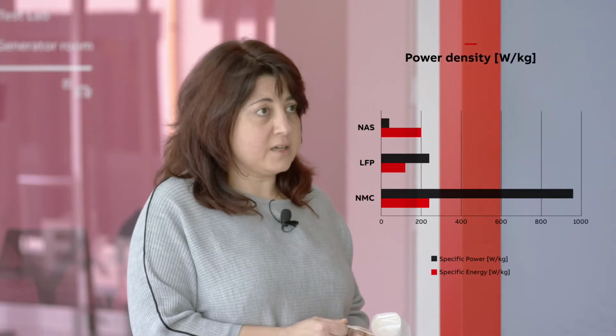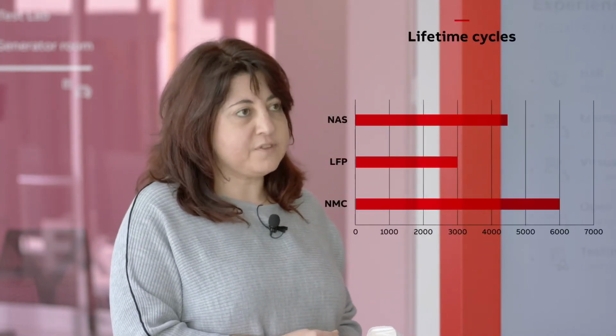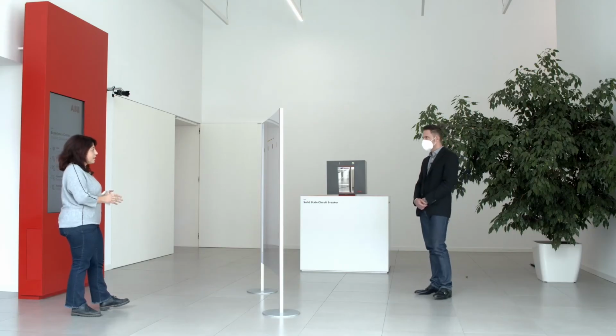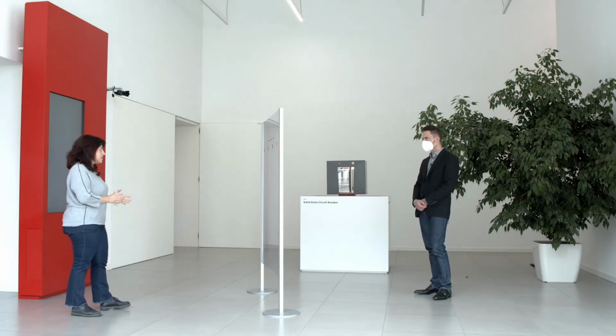The performances of this technology are always very good because the energy density of the cell is around 200 watt-hour per kilogram, and the lifetime is also very good. The same as the lithium-ion battery, the sodium-sulfur battery also has a low intrinsic safety level. This means that for both technologies, it is necessary to integrate in the energy storage systems the proper protections and battery management system in order to reach an adequate level of intrinsic safety, to avoid abuse conditions and manage the system in a correct way.